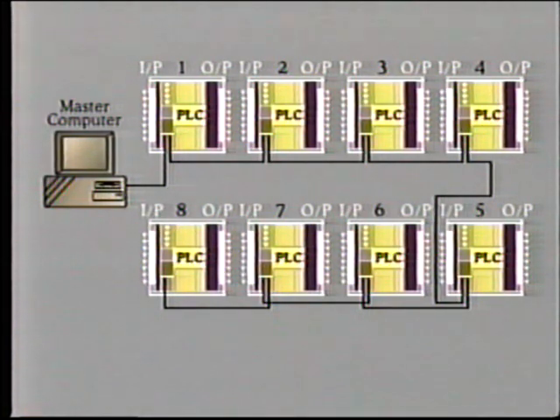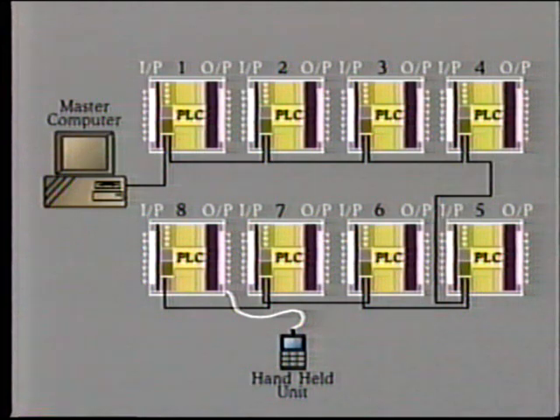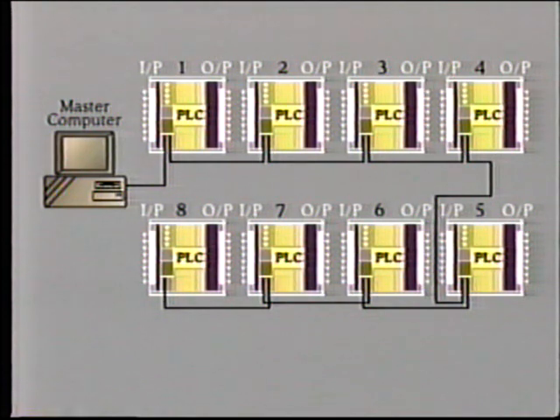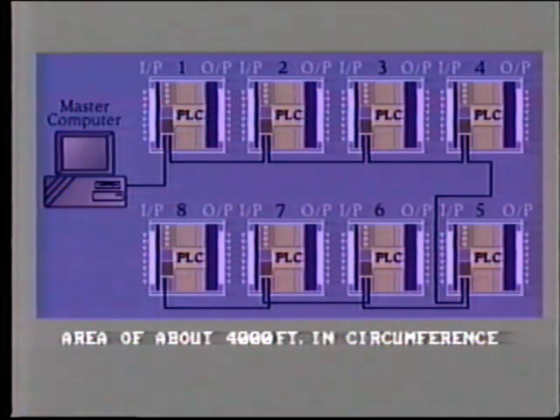In one arrangement, up to 8 PLCs can be connected together via a common communications system. The advantage of this is that any one of the PLCs can be accessed from a single unit. For example, the programmer can be plugged into, say, PLC number 8, and then used to troubleshoot or program this PLC, or monitor any one of the other 7 PLCs. Another advantage is the facility for extracting data from all 8 PLCs and feeding this into a central computer. At the central location, we can learn what each PLC is doing at its individual location. In this type of arrangement, the total distance involved is usually limited to an area of about 4,000 feet in circumference, unless special arrangements are made to boost communications signal strength.